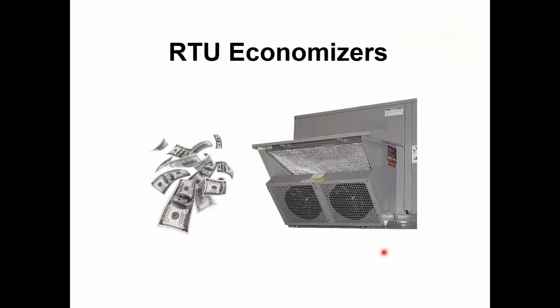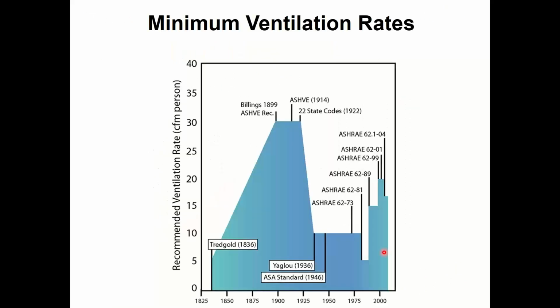All right, economizers, the last main topic that we really want to dive into today. There's a couple quick questions here. Reza asks, does the damper open during unoccupied time for free cooling? I'm assuming you're talking about if I tie an occupancy schedule to my economizer damper. Most people don't do that, but if I did, like the code requires and like I would want to do to save energy, yes, the damper can still open for free cooling mode.